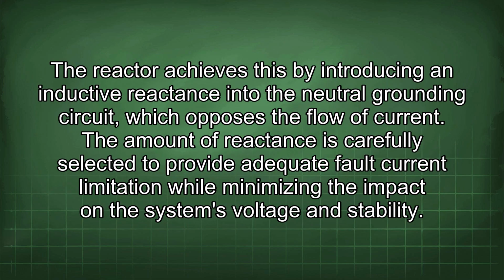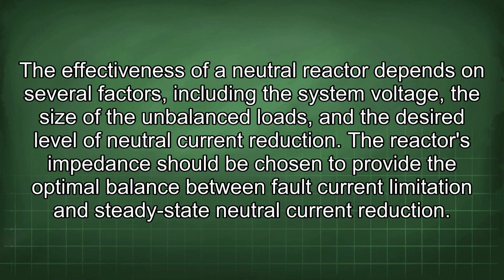The reactor achieves this by introducing an inductive reactance into the neutral grounding circuit, which opposes the flow of current. The amount of reactance is carefully selected to provide adequate fault current limitation while minimizing the impact on the system's voltage and stability. The effectiveness of a neutral reactor depends on several factors, including the system voltage, the size of the unbalanced loads, and the desired level of neutral current reduction. The reactor's impedance should be chosen to provide the optimal balance between fault current limitation and steady-state neutral current reduction.